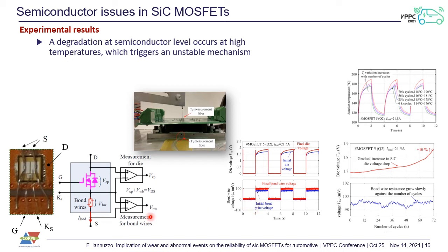The bond wire voltage drop was also increased, but we were able to discriminate the difference between the semiconductor alone and the bond wire alone. You can see the results in this picture, where the semiconductor voltage drop is the red curve and the bond wire voltage drop is the blue curve. There's a slight increase in the bond wire, some ups and downs, but the semiconductor voltage shows a definite and remarkable increase, around 10%, as pointed out in this picture.